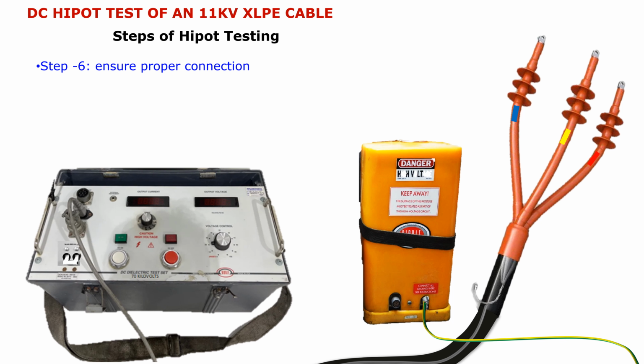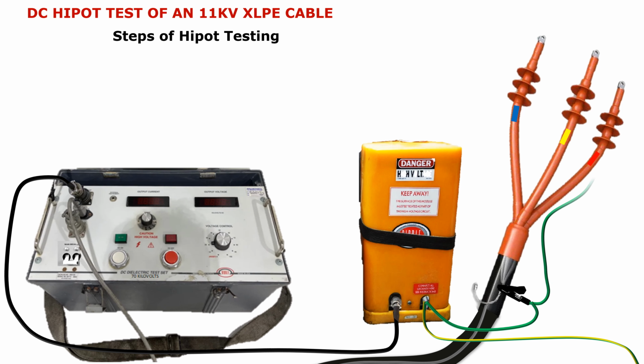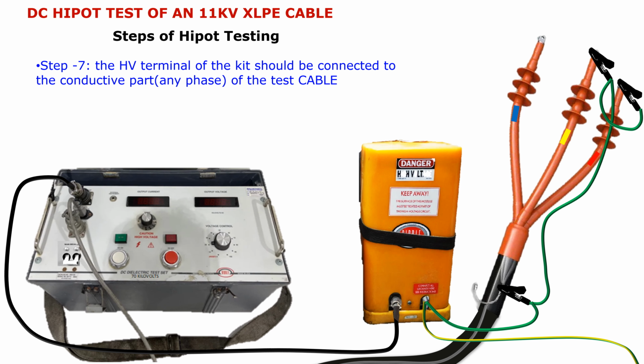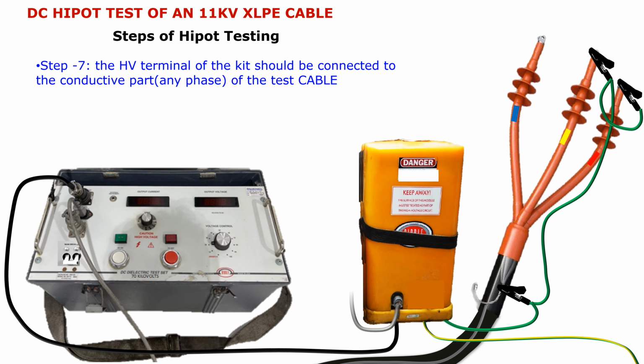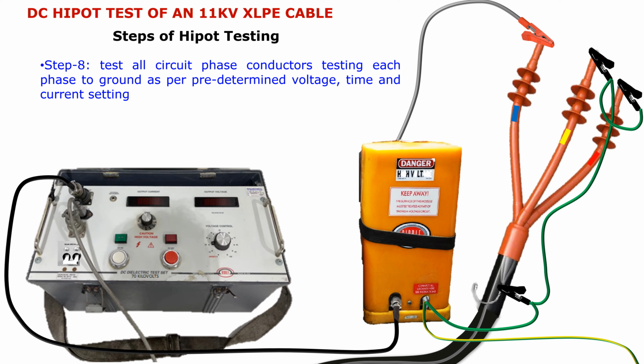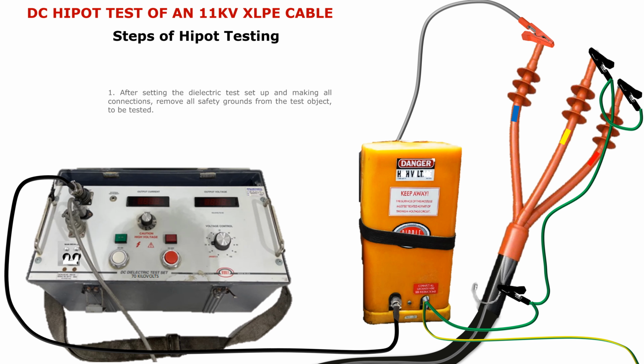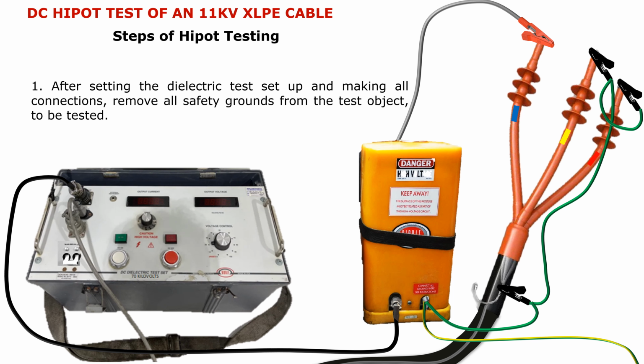Step 6. Ensure proper connection. Step 7. The HV terminal of the kit should be connected to the conductive part, any phase of the test cable. Step 8. Test all circuit phase conductors, testing each phase to ground as per predetermined voltage, time and current setting. After setting the dielectric test setup and making all connections, remove all safety grounds from the test object to be tested.